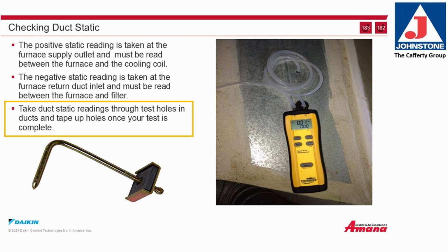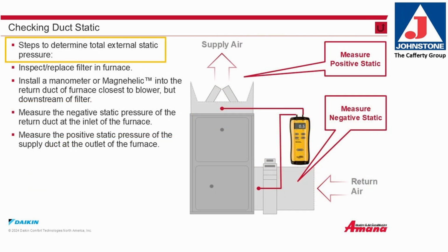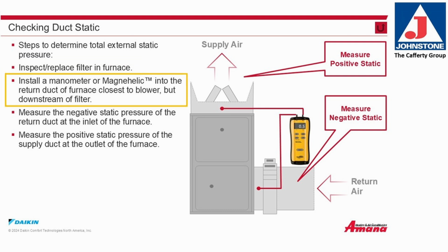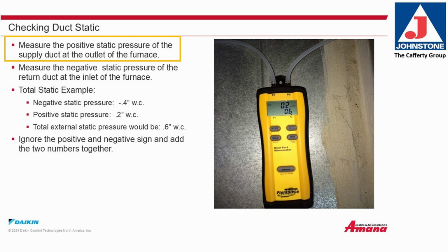Steps to determine total external static pressure. Inspect and/or replace the air filter in the furnace. Install a manometer or magnehelic into the return air duct of the furnace closest to the blower but downstream of the filter. Measure the negative static pressure of the return duct at the inlet of the furnace. Measure the positive static pressure of the supply duct at the outlet of the furnace. Again, measure the positive static pressure of the supply duct at the outlet of the furnace. Measure the negative static pressure of the return duct at the inlet of the furnace.